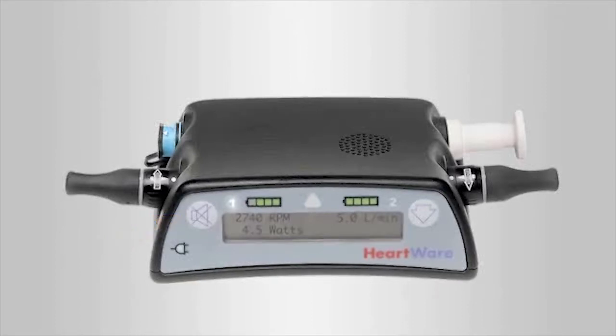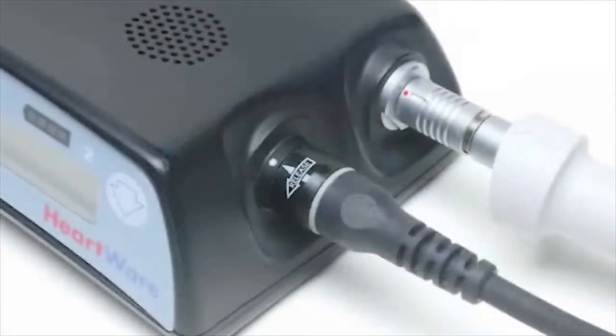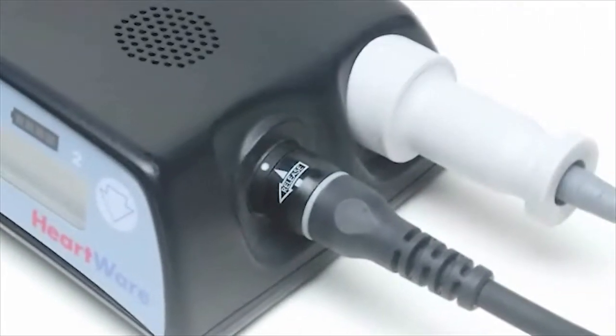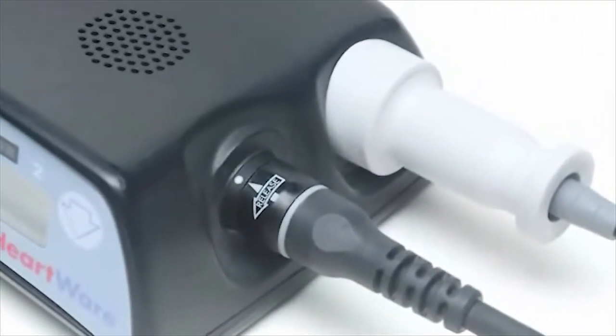There are 4 connectors on the controller, 1 driveline connector, 2 power supply connectors, and 1 monitor connector, which is also used for the alarm adapter. The silver driveline connector should always have the driveline cover in place. When properly positioned, the driveline connector will not be visible.